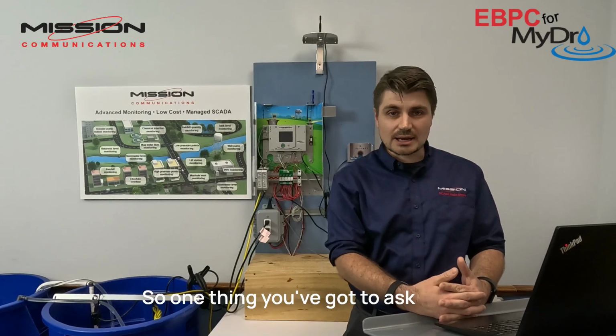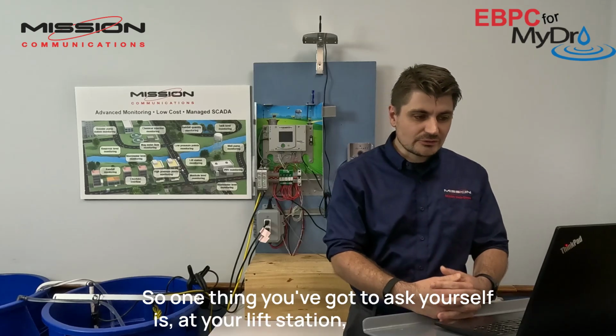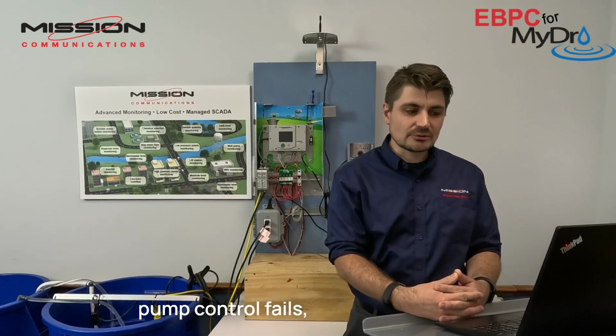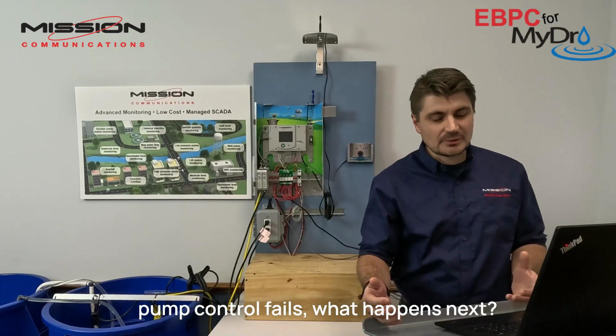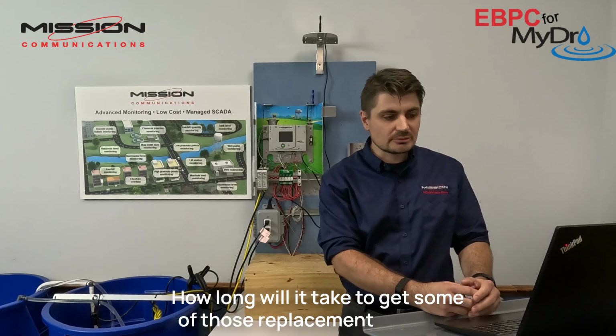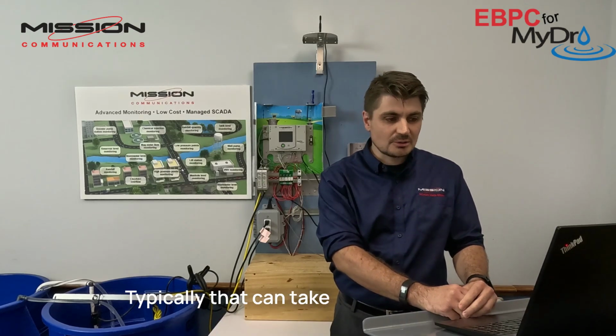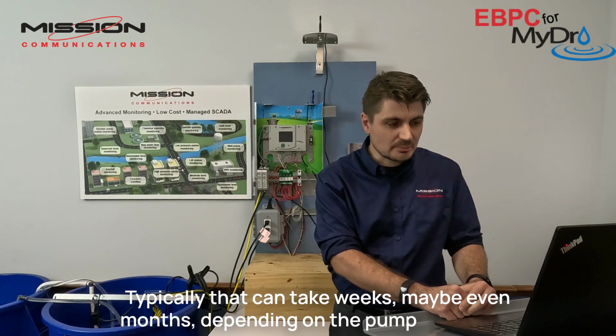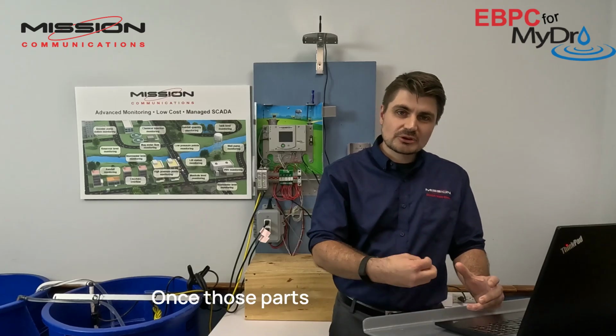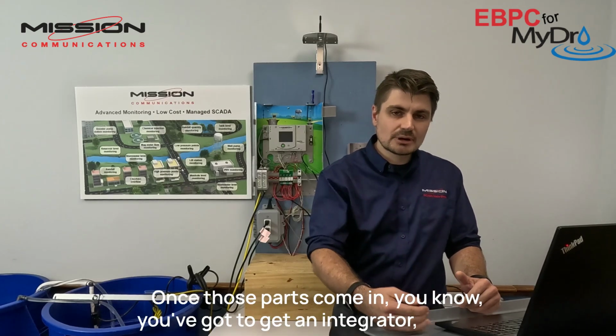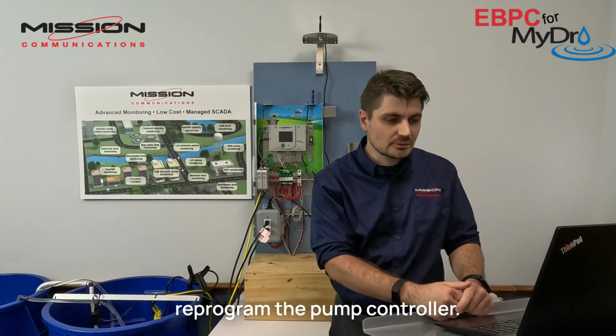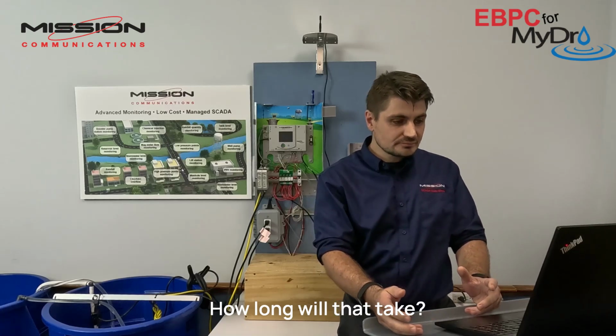So one thing you've got to ask yourself is, at your lift station, if your primary pump control fails, what happens next? How long will it take to get some of those replacement parts in? Typically that can take weeks, maybe even months, depending on the pump controller. Once those parts come in, you've got to get an integrator, possibly reprogram the pump controller. How long will that take?